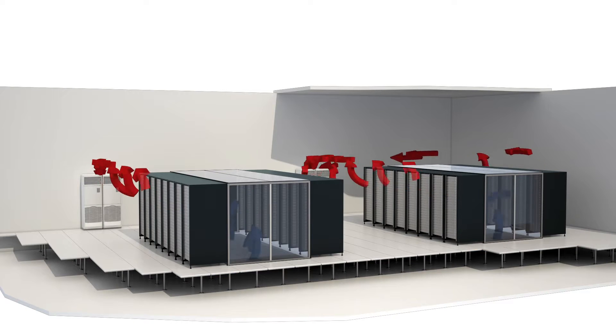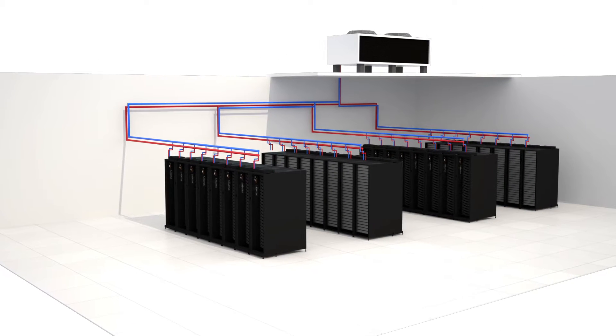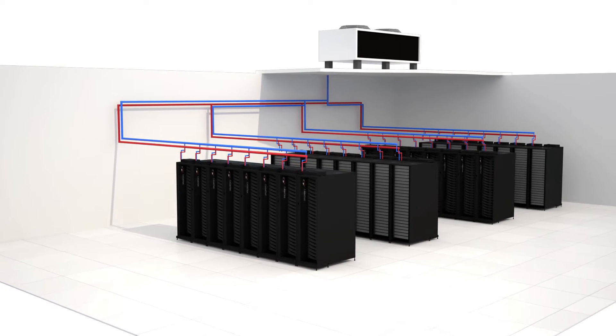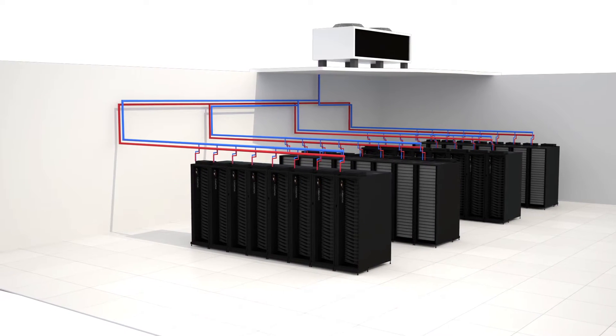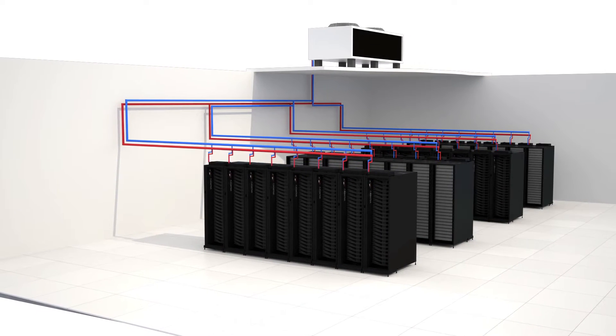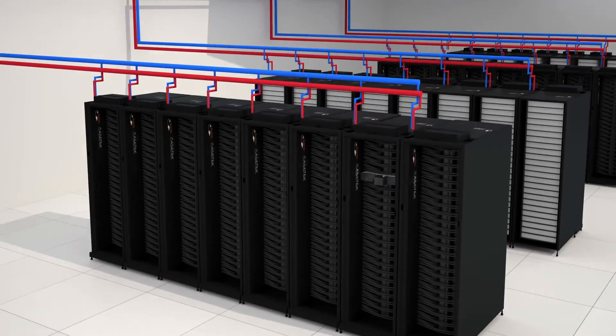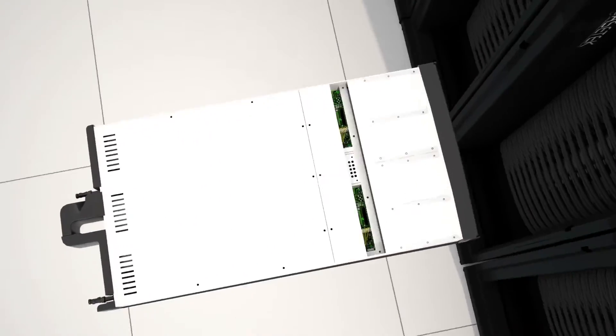Cooling accounts for 50% of annual operating costs in a traditional air-cooled data center like this one. ISAC integrates with Asetek's RackCDU, completely eliminating the need for computer room air conditioners to cool servers inside the data center. The air stays inside the server and recirculates rather than exiting and heating up the data center. In addition, the need for cold aisle containment and raised floors is also eliminated.